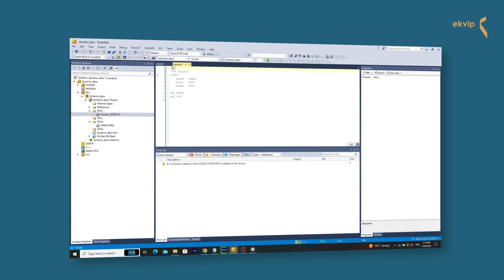If we want to create a structure in TwinCAT 3 dynamically, we obviously need a structure. In the declaration of the structure you insert the attribute EnableDynamicCreation in the first line. The new operator can only be applied to function blocks or DUTs from libraries and to function blocks or DUTs with the attribute EnableDynamicCreation. If the interface of such a function block or DUT is changed, TwinCAT issues an error message.